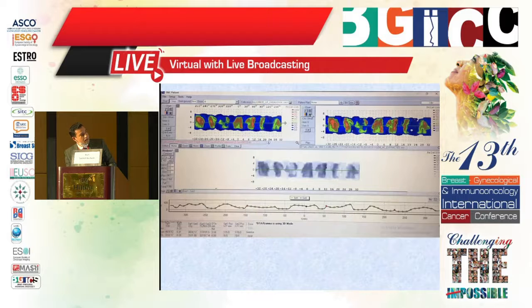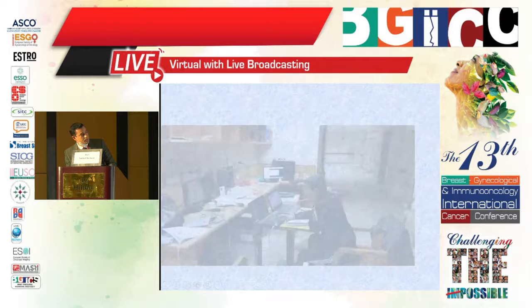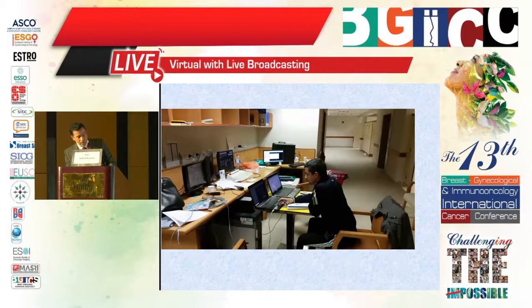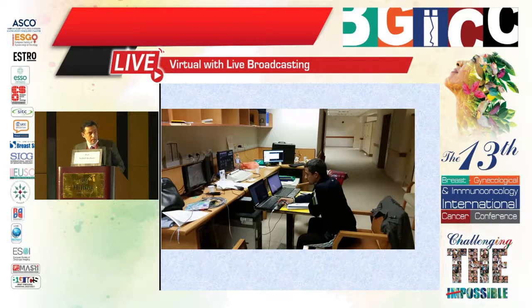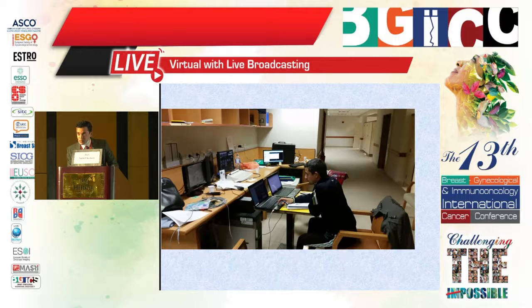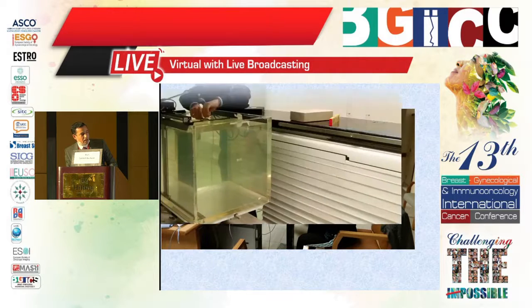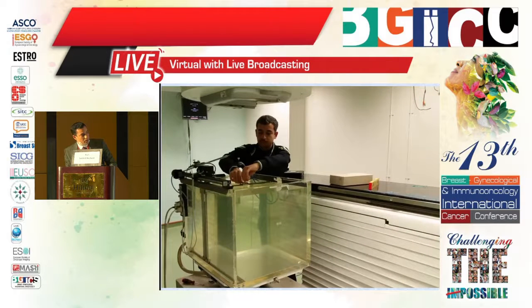This is a comparison of the planned dose map and the measured one, point to point. To get accurate treatment, you should have a very thorough quality assurance program for your machines — daily, weekly, monthly, and annual QA at your hospital.